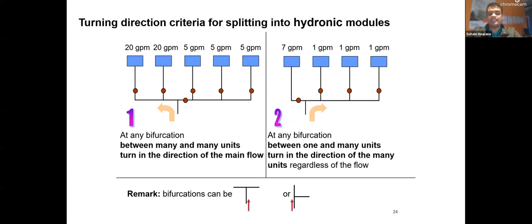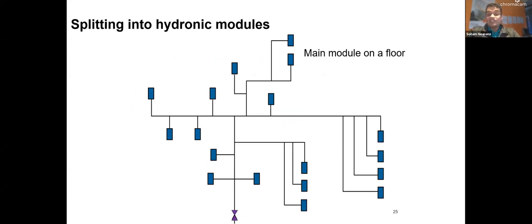So let's go and start placing those valves on our simplified plan together now, okay? So as I said, we'll start with the pump. So close to the pump, we already have a manual balancing valve. The purple ones are my partner valves, okay? So this is our main module. So we start moving up on the module. And now we reached a takeoff here. So, I've got one terminal. So I know that's the final one. So I place a manual balancing valve and I'm marking this with red just to differentiate that from a partner valve. So I place a manual balancing valve on each of these terminal units. And then I get back on my main line, move further, got one terminal unit, place your manual balancing valve.